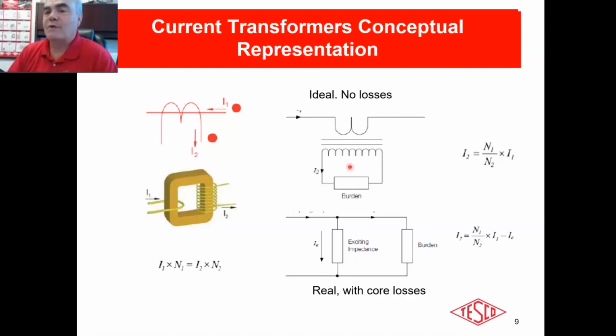Okay, so we have our transformer, and here's our primary, here's our secondaries. In a perfect world, I have no losses whatsoever, and there's an engineering model of an ideal world with no losses. However, we don't live in an ideal world. I know, shocking to some of you, but it's true. We don't really live in an ideal world. Every transformer requires a certain amount of current to begin working. We call it an exciting impedance. It's not really overly exciting, but it is to that transformer. So it takes a certain amount of that primary energy to actually get the transformer working. Because of that, transformers are always something less than 100% accurate. Not much. It's very, very small. It can be measured, but it is very, very small in terms of its loss. There is always something, though.